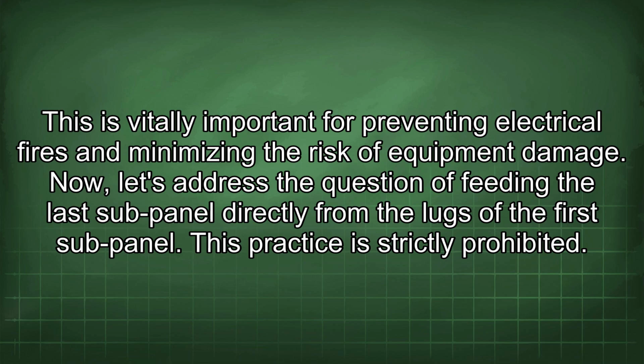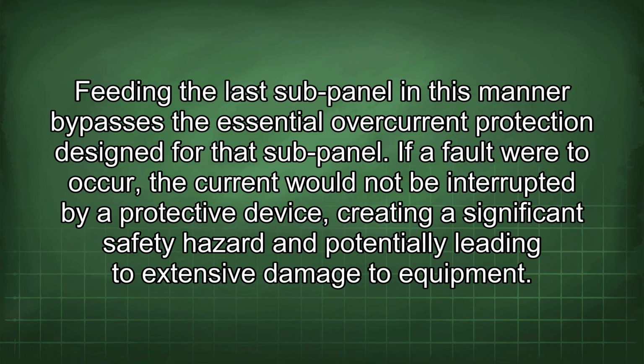Now, let's address the question of feeding the last sub-panel directly from the lugs of the first sub-panel. This practice is strictly prohibited. Feeding the last sub-panel in this manner bypasses the essential overcurrent protection designed for that sub-panel. If a fault were to occur, the current would not be interrupted by a protective device, creating a significant safety hazard and potentially leading to extensive damage to equipment.